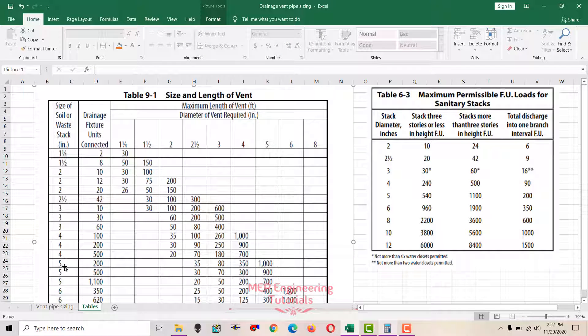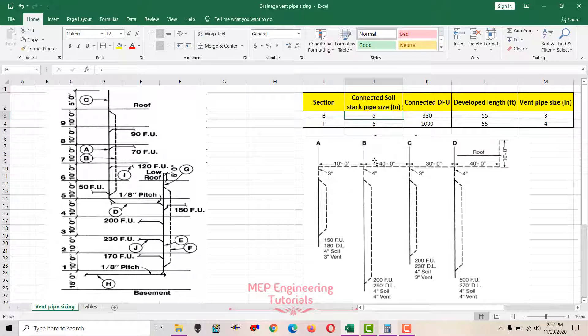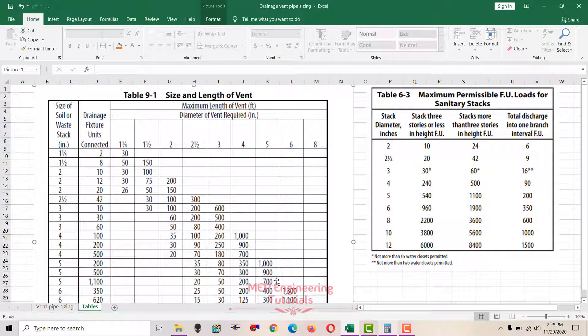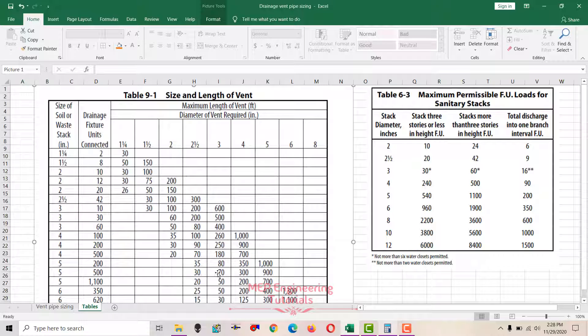We use Table 9-1. Soil stack pipe size is 5 inches and fixture units are 330 — between 200 and 500, so we go to 500. The pipe sizes along the top are the vent pipe sizes; the rows are drainage fixture units; and the columns in between are the developed lengths. Developed length of 55 is between 30 and 70, so we go to 70. The resulting vent stack pipe size is 3 inches.